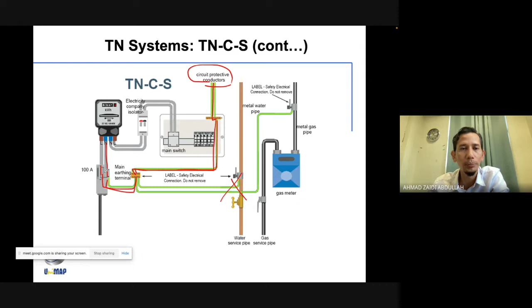The most important thing is knowing the connection - let's say this is your load, socket to light, you must have an earthing cable, and from the earthing cable tap to the main earthing in the DB, and from the DB it's connected to the main earthing terminal from the supply before connecting to the neutral at the transformer from TMB.